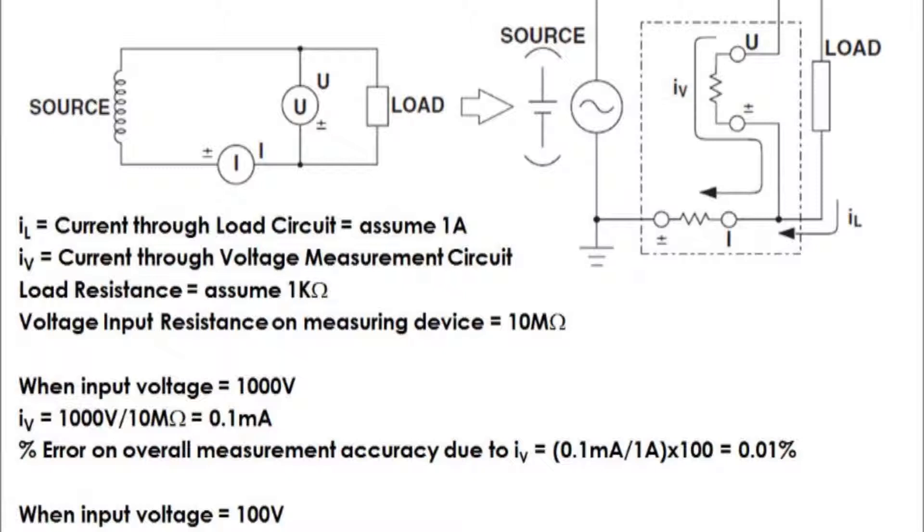Similarly, if the input voltage was 100 volts, IV is 0.01 milliamps and the effect of IV on the overall measurement accuracy is 0.001%. Therefore, when measuring large currents, placing the voltage measurement device as shown in this circuit will minimize the error on the overall current measurements and thereby also minimize the error on the overall measurement accuracy.